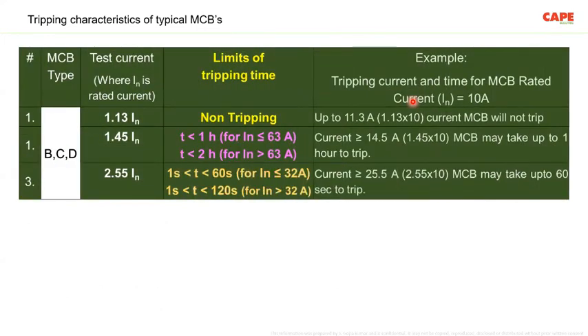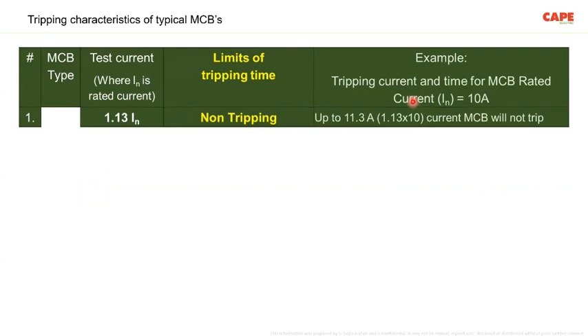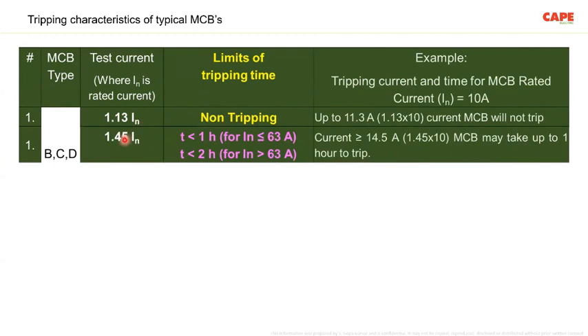Also, people always think that in case of any problem, the MCB will trip, which is also not correct. For any type of MCB, B, C, or D, if the current is 1.13 times the nominal rated current, say I put a 10 amps MCB, up to 11.3 amps the MCB need not trip. Up to 1.45 times its rated current, MCBs of less than or equal to 63 amps can take up to 1 hour to trip. Higher than 63 amps, it can take up to 2 hours to trip.